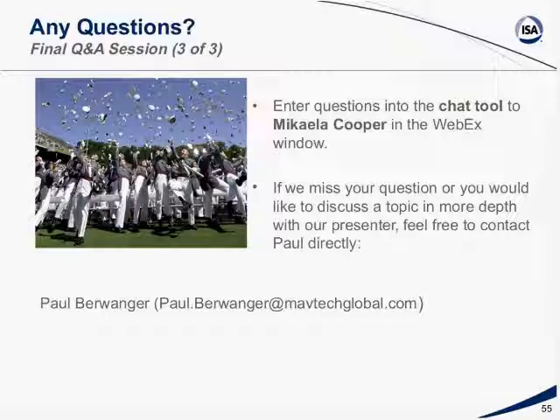So you may have somebody who's getting an excessive number of alarms, but it's really due to the fact that you've got this person responsible for too large an area. And rationalization is not going to get you there. I mean, one of the worst things that can happen is you go and rationalize something and you have the same number of alarms, because all the alarms are valid. And so that's when you really take a look at it.